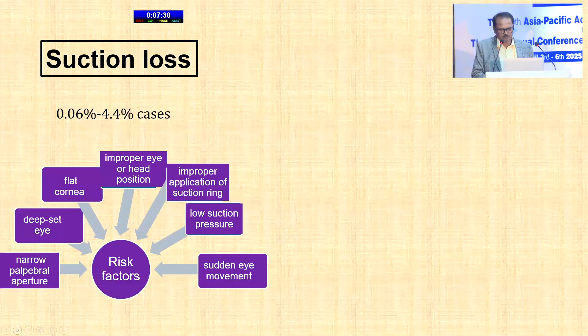So what are the causes of suction loss? Most of the time it is in the patient's eye, if we are not taking preoperative care: a patient with a narrow palpebral aperture, a very apprehensive patient, a deep set eye, a flat cornea, or improper position of the patient's eye. There may also be improper application of the suction ring: you have not properly chosen the size of the ring, you have not applied the suction properly, the suction pressure is low, or there is sudden movement of the patient's eye. Any of these can cause loss of suction.